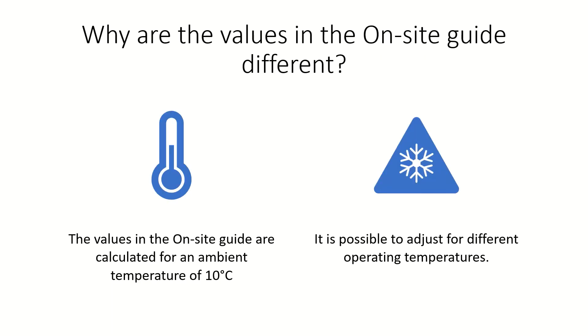So the next question is, why are the values in the on-site guide different? The answer is because the values in the on-site guide are calculated based on an ambient temperature of 10 degrees C. This makes sense because it's often colder when working on-site, and so this can be a useful guide.